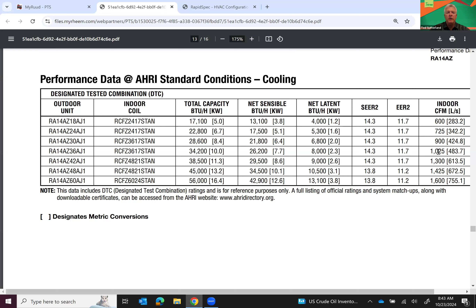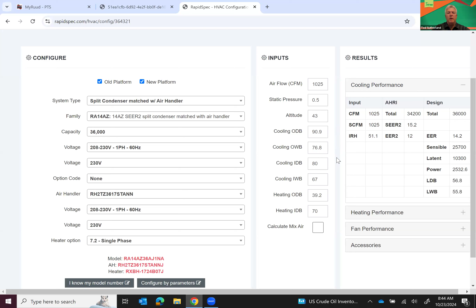So we need to go back into RAPIDSPEC, and we need to change that to 1,025 CFM. All right. Now, if your design with your ductwork is going to be at a different static pressure, then you'll need to change that as well. Okay. And you can see that that's changed our AHRI. And now here's what our total design is on that system at those conditions that we've listed here. And that's mainly because of this information that we have on our outdoor and wet bulb that was drawn from the Daytona weather station that we have listed here. Okay, so just be careful when we're talking about your airflow and your CFM.